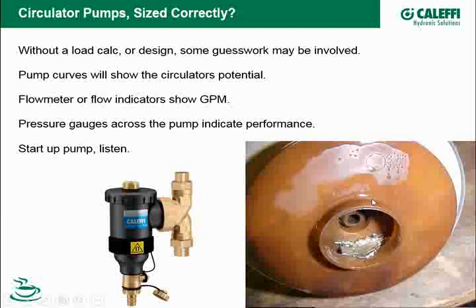They'll start wearing on this wear ring and stuff like that. So I can't stress how important it is to have a good dirt separator in your system, whether it's a brand new system you're putting in or a system that you're going to do some retrofit or a service call. This is another version that we make.